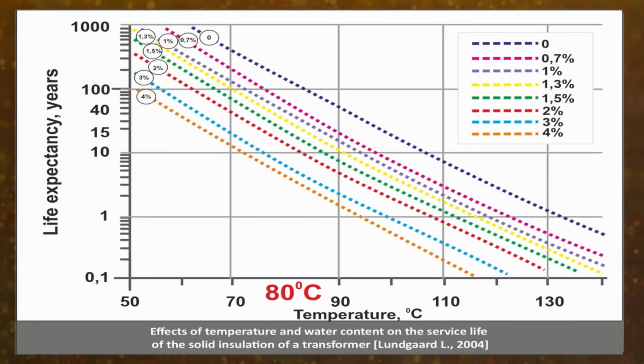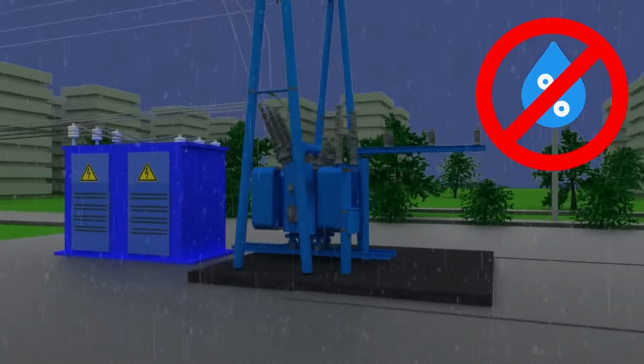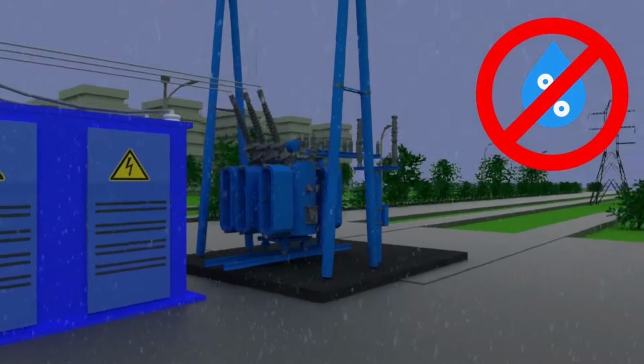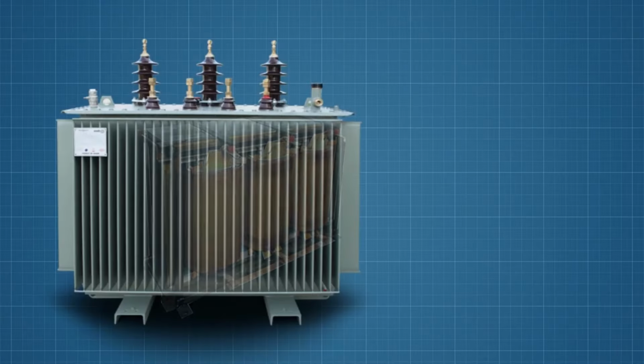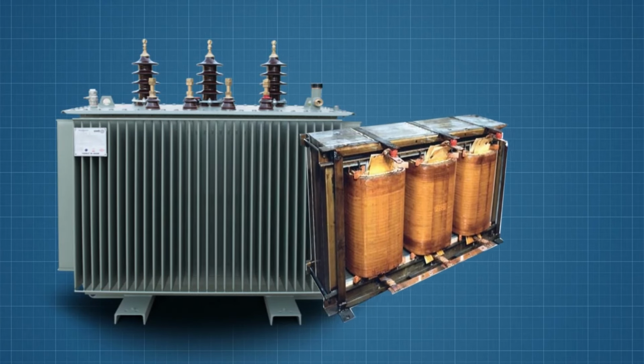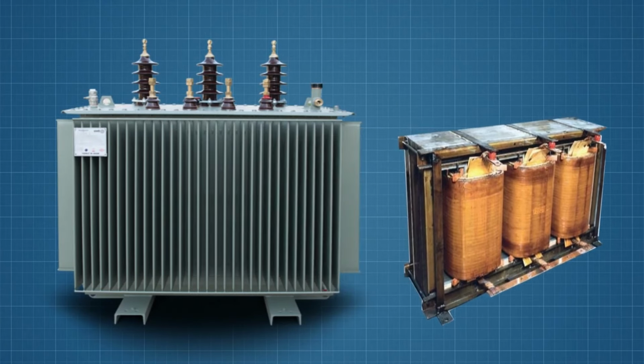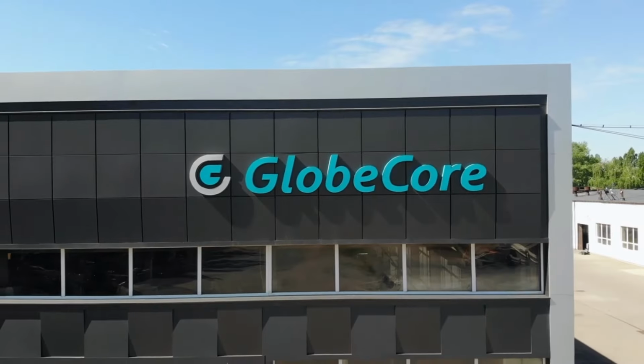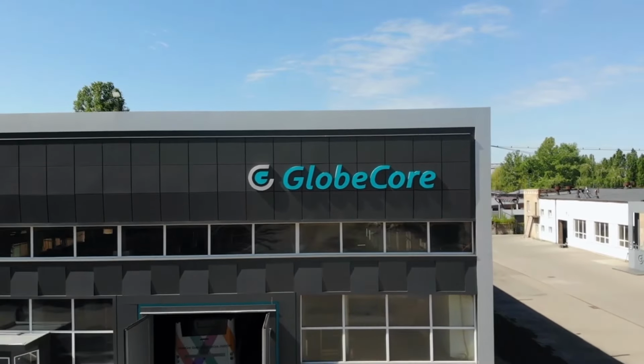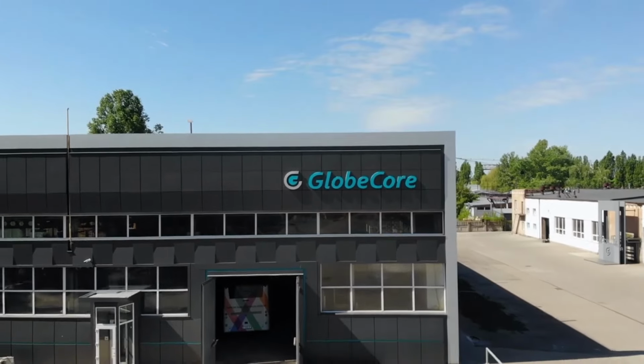Graphs show that the higher the temperature and the water content, the shorter the lifespan of solid insulation. Heating of the windings and the insulation in a loaded transformer is not something that can be changed. However, by reducing the water content, the lifespan of the solid insulation and the entire transformer can be increased. Depending on the location, insulation drying may or may not involve extraction of the windings from the transformer tank. GlobeCore has developed technologies and equipment for both cases.